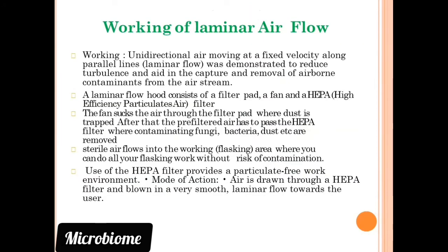Now next we will see the working of laminar airflow. Unidirectional air moving at a fixed velocity along parallel lines, that's why it is called laminar flow, was demonstrated to reduce turbulence and aid in the capture and removal of airborne contaminants from the airstream. So there is a continuous flow of air, and when that air passes through the HEPA filter, the contaminants get trapped. A laminar flow hood consists of a filter pad, a fan, also called a blower, and a HEPA, that is a high efficiency particulate air filter.